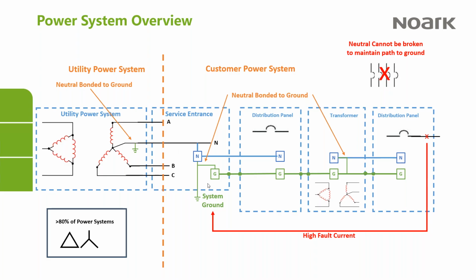But also the system ground is connected to what's called bonding, and every enclosure needs to be bonded to that ground system. The reason is that if you've got a fault way down at the bottom end of the power system, that bonding to ground provides a very low impedance path back to ground, and it makes the breaker operate very quickly in the event of a fault. The other thing the bonding to the enclosure does is ensure that the enclosure and the person touching it doesn't become the lowest impedance path to ground. This is all designed for safety, and this grounding is very important, and you'll see where this system ground comes into play as we start talking about service entrance.